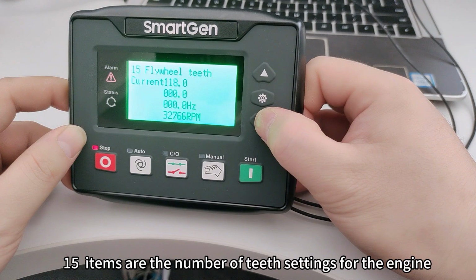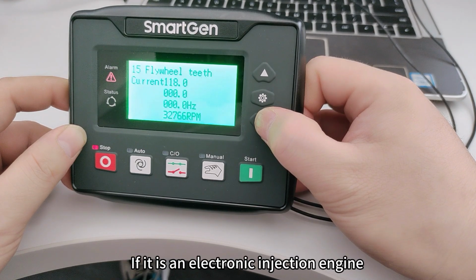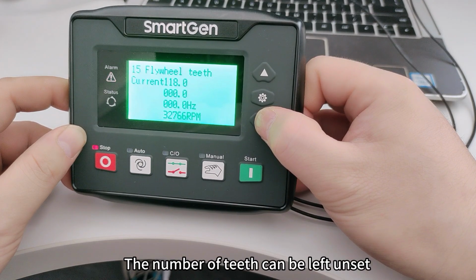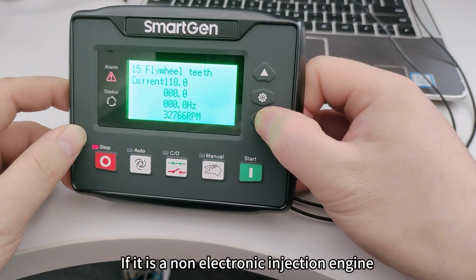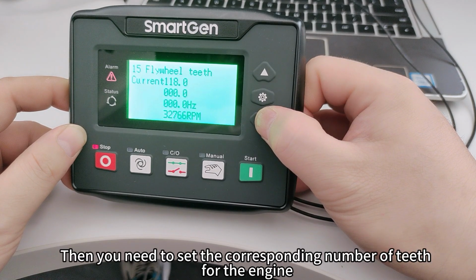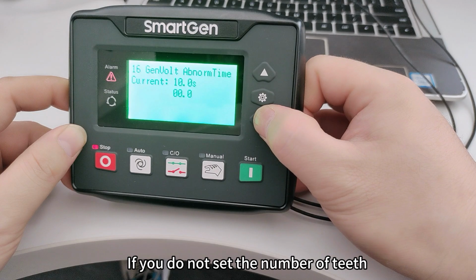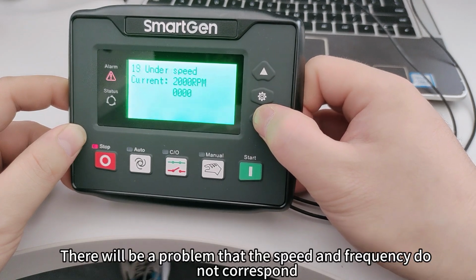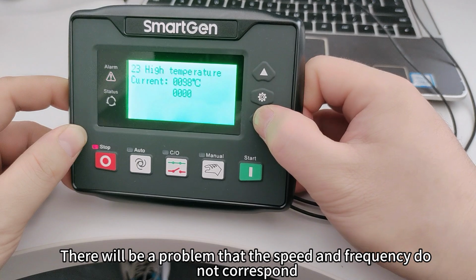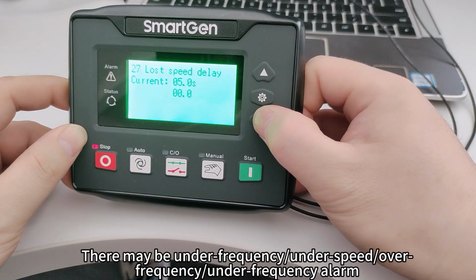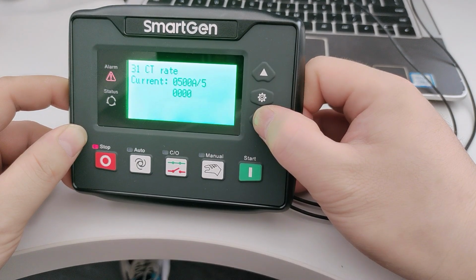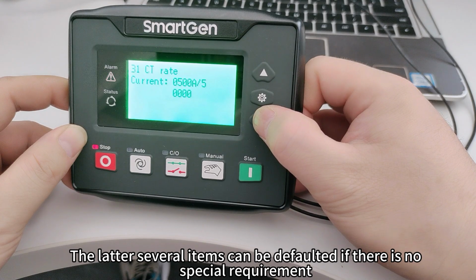Item 15 is the number of teeth setting for the engine. If it is an electronic injection engine, the number of teeth can be left unset. If it is a non-electronic injection engine, then you need to set the corresponding number of teeth for the engine. If you do not set the number of teeth, there will be a problem that the speed and frequency do not correspond. There may be under frequency, under speed, over frequency, or under frequency alarms. The latter several items can be left at default if there is no special requirement.